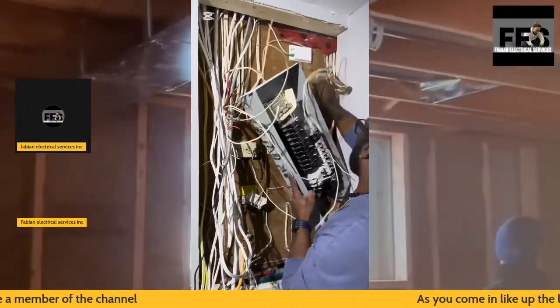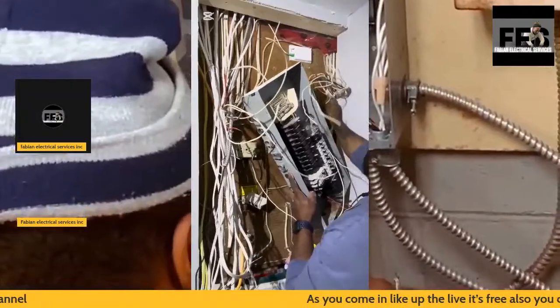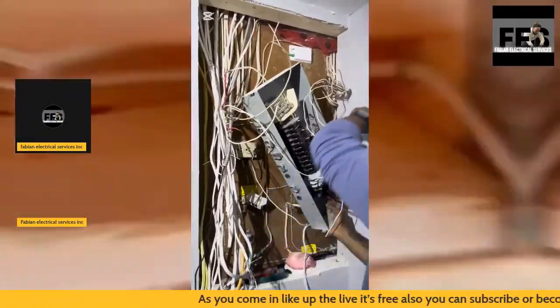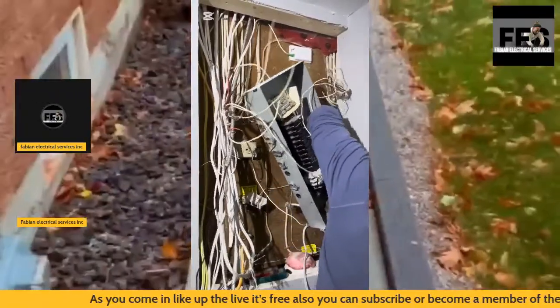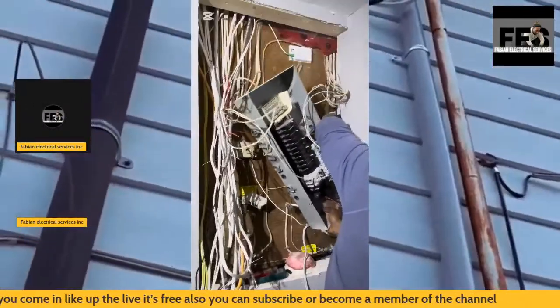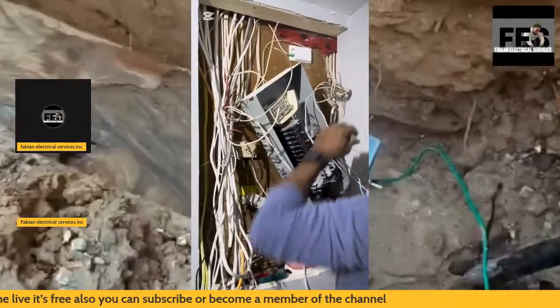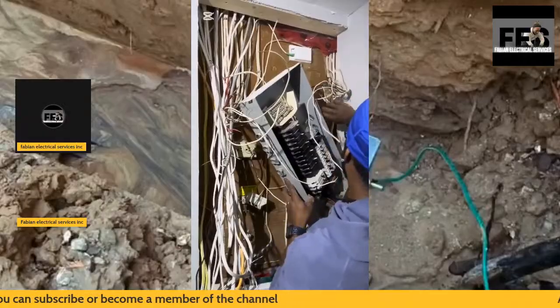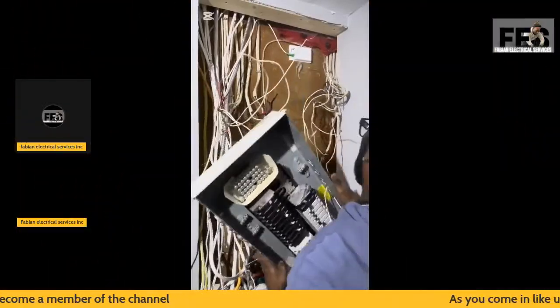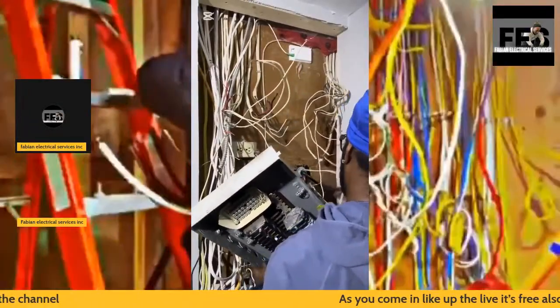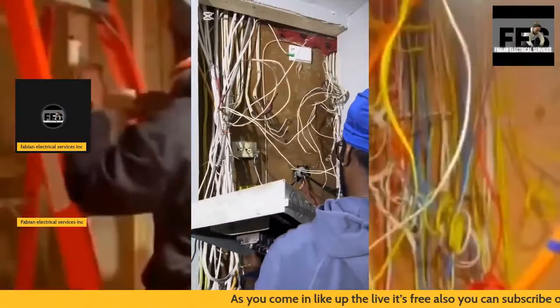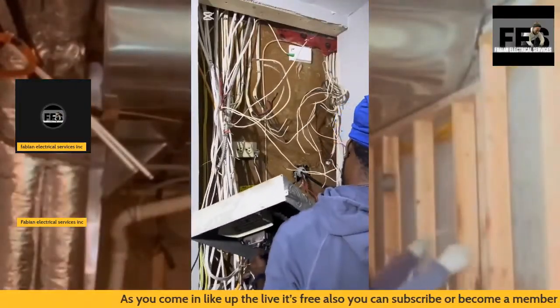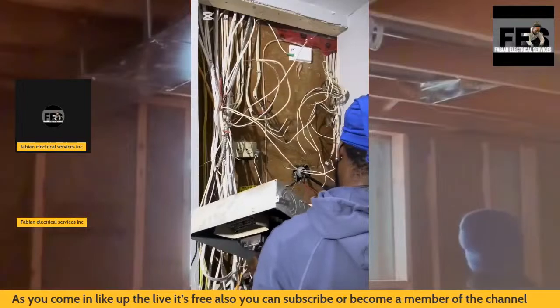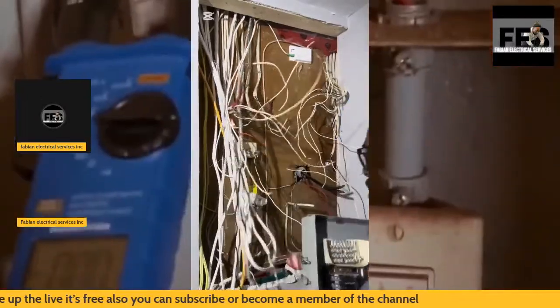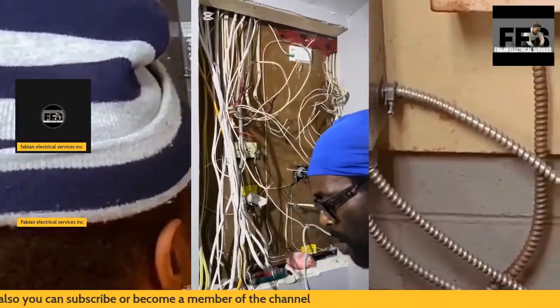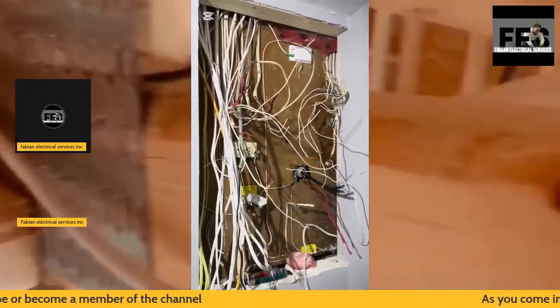In code 2024, this is what I use. There's nothing wrong with oversizing wire, and then using the proper breaker size for the actual device that you're going to be using. So for instance, if you have a 15 amp GFI, have a 15 amp breaker on the other end at the panel ready to power it up.